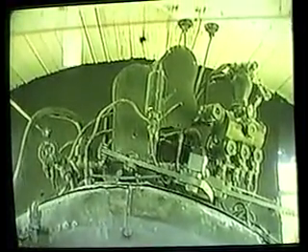Also remember to bear in mind that as your steam pressure goes higher, the higher the temperature required to cause the water in the boiler to boil. At 180 pounds steam pressure, water boils at 372.886 degrees.